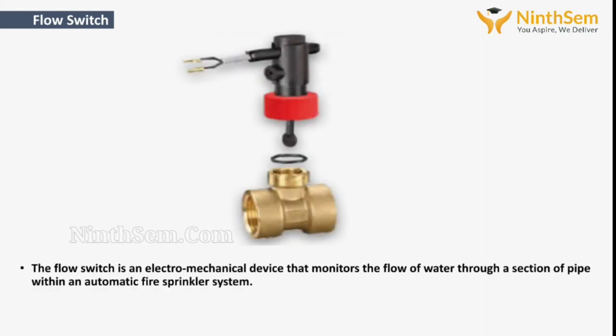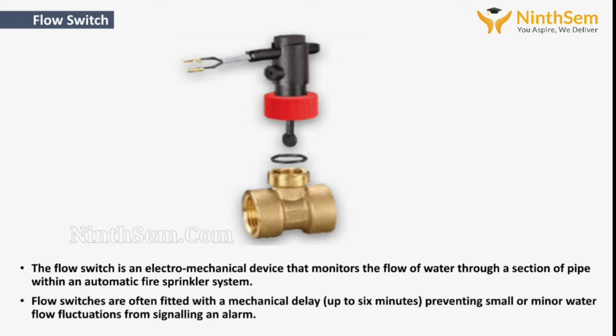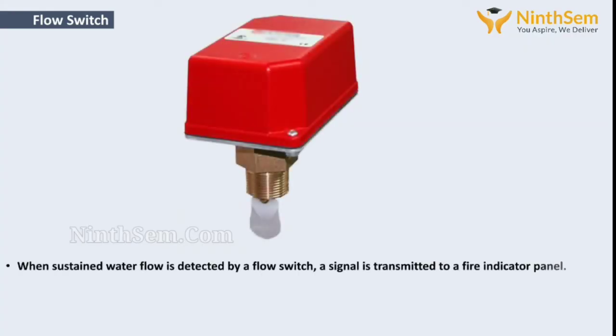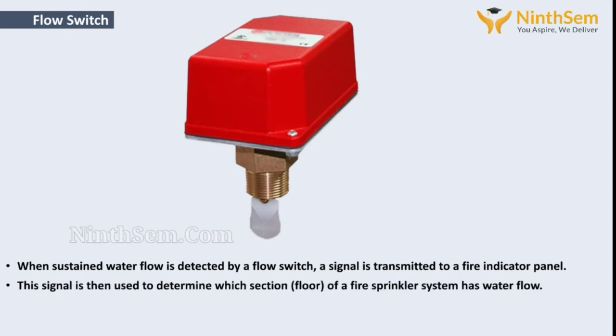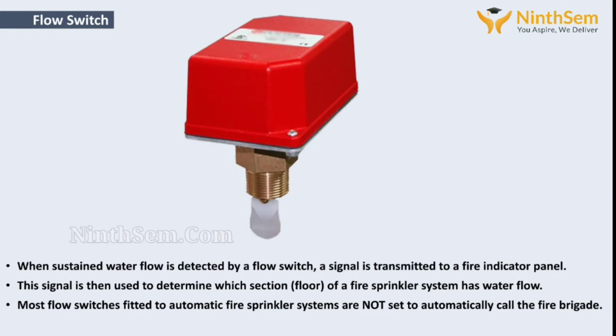Next, the flow switch. The flow switch is an electromechanical device that monitors the flow of water through a section of pipe within an automatic fire sprinkler system. Flow switches are often fitted with a mechanical delay of up to 6 minutes, preventing small or minor water flow fluctuation from signaling an alarm. When sustained water flow is detected by a flow switch, a signal is transmitted to a fire indicator panel, and the signal is then used to determine which section or floor of a fire sprinkler system has water flow. We have to note one thing: most flow switches fitted to automatic sprinkler systems are not set to automatically call the fire brigade. In India, we don't use such kind of arrangement. Mostly we are not using such kind of arrangement.